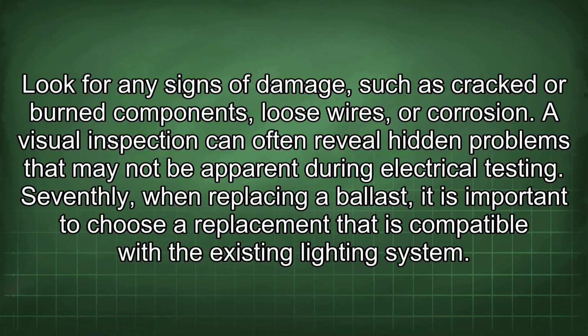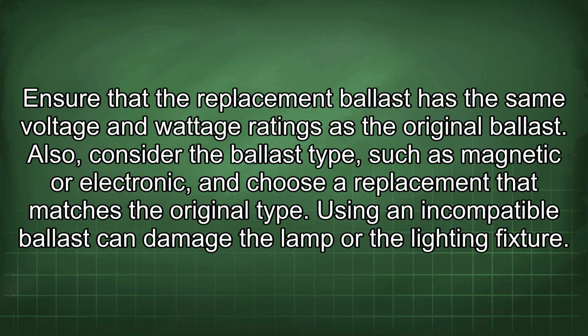Seventhly, when replacing a ballast, it is important to choose a replacement that is compatible with the existing lighting system. Ensure that the replacement ballast has the same voltage and wattage ratings as the original ballast. Also, consider the ballast type, such as magnetic or electronic, and choose a replacement that matches the original type. Using an incompatible ballast can damage the lamp or the lighting fixture.